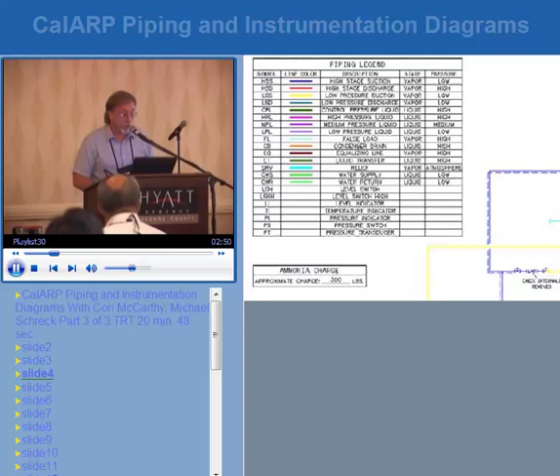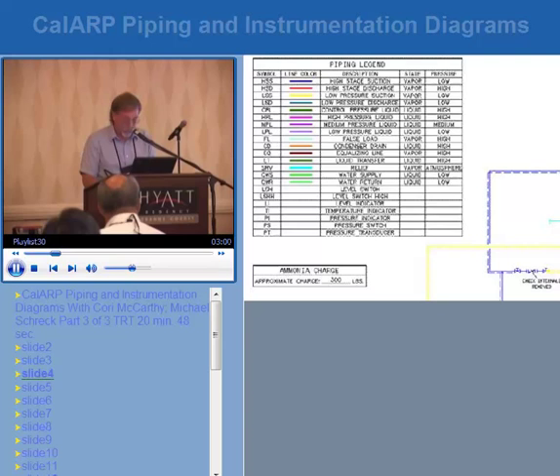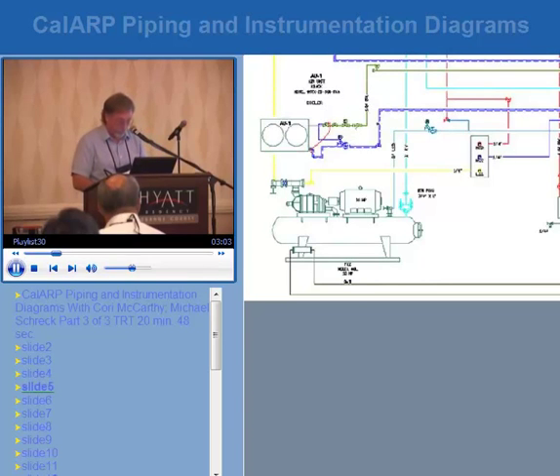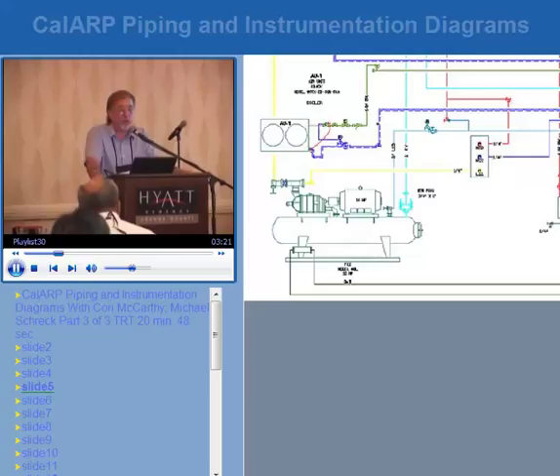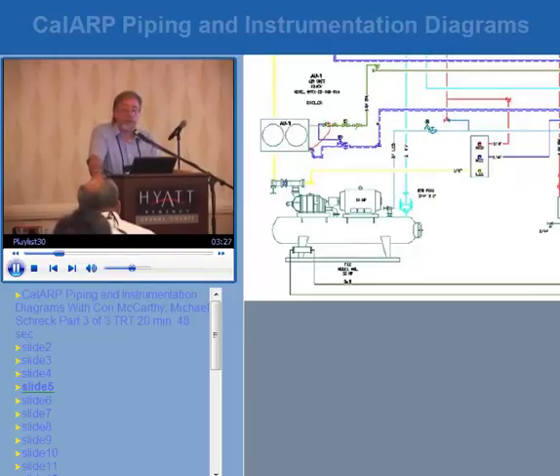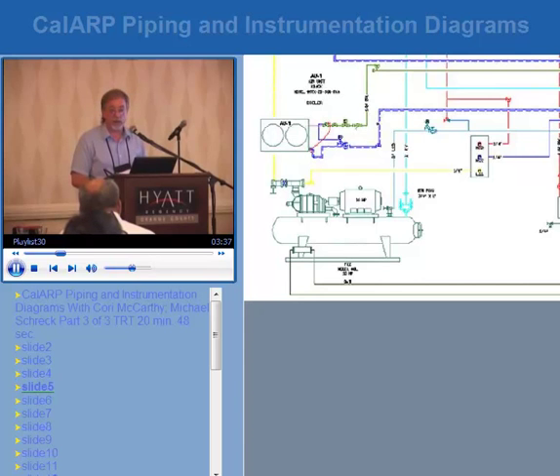Many times on the P&IDs, if you're wondering what the charge is in the system, it'll be on there — very good information for the responder to know the quantity of hazardous chemicals involved. Zooming in on a section, we have an air unit called AU1 — it shows the model and make of that unit, excellent information, and the controls for ammonia flow into and out of the unit, critical for zone and component isolation. However, there are no valve numbers whatsoever — this is the beginning of a P&ID. It's color-coded and gives a lot of information but is not yet complete.